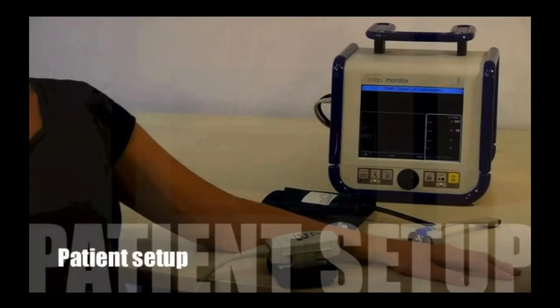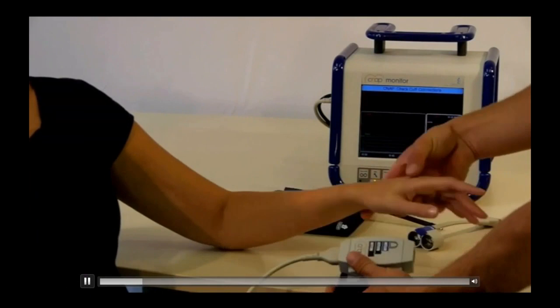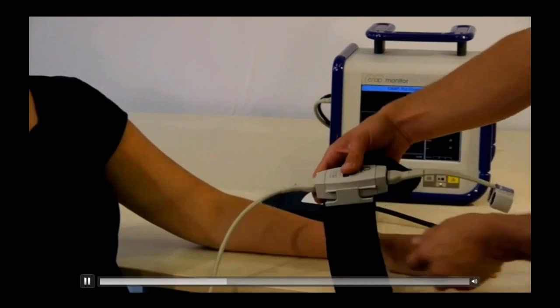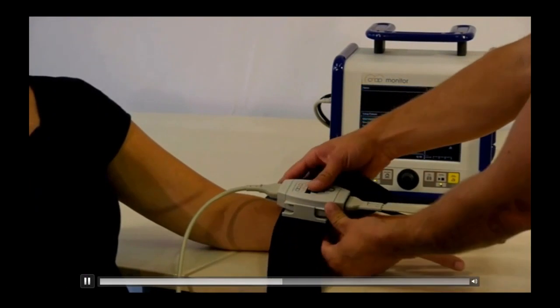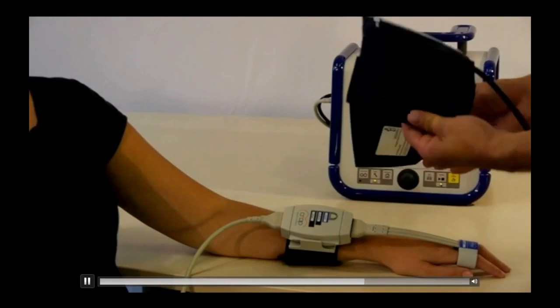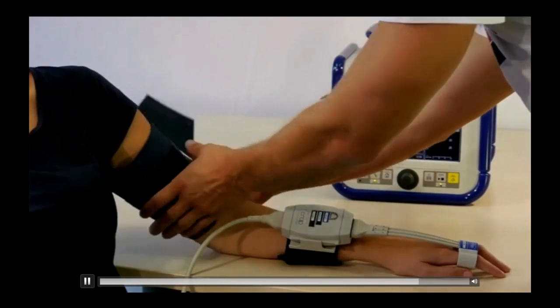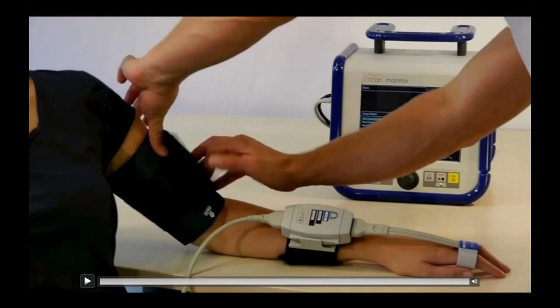For patient setup, select the right finger sensor size by aligning the patient's index or middle finger with the color label on the forearm controller. Once connected, make sure the sensor goes all the way up on the proximal phalanx of the finger, avoiding the knuckles. Before closing the strap on the forearm controller, make sure the slider is in the middle position to allow some arm movement. The upper arm cuff for CNAP calibration can go ipsilateral or contralateral — ensure cuff circumference matches the patient's arm and the radial marker is properly positioned.